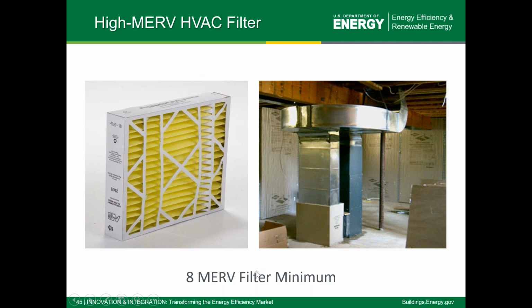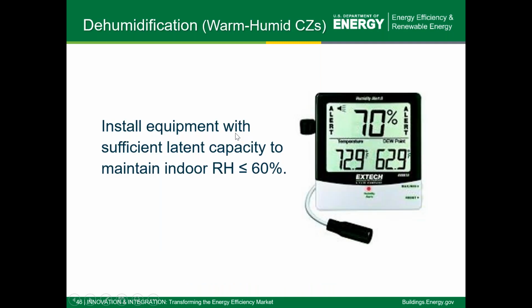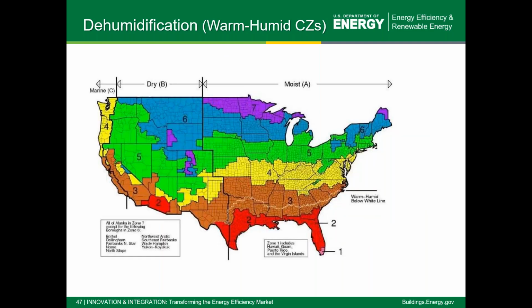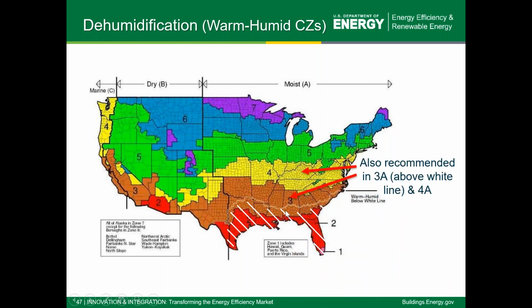High capture filtration is required by Indoor Air Plus, at least MERV 8 or higher. Then also, in areas of the country that are more warm and humid, as we'll see in a map, auxiliary equipment with enough capacity to maintain indoor relative humidity at or below 60% is required to control indoor RH levels throughout the year. The area where that's required is shown in the white striped area in the southeast. However, a number of builders are implementing that measure elsewhere, even though it's not required, just for better humidity control, such as the upper regions of climate zones 3A and 4A as shown on the map.